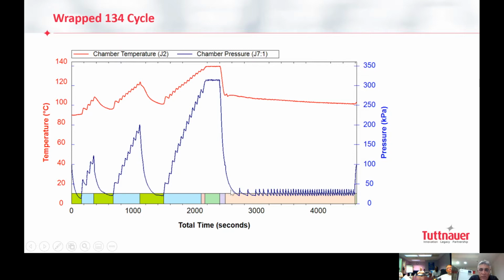So we are releasing from the bottom in order to get free of all the condensation. While we reach the 100 kPa here, this point, you see the small gap here. Then we are closing the bottom exhaust line, fast exhaust, and starting with the vacuum system, which is from the top. The reason it is from the top is to make sure that we are getting free only from the gas. I don't want condensation or water to get to the vacuum pump, because the vacuum pump is a membrane, it's hydrophobic.